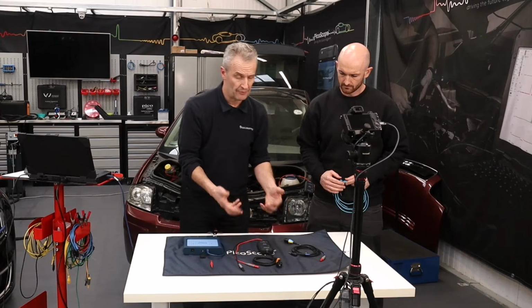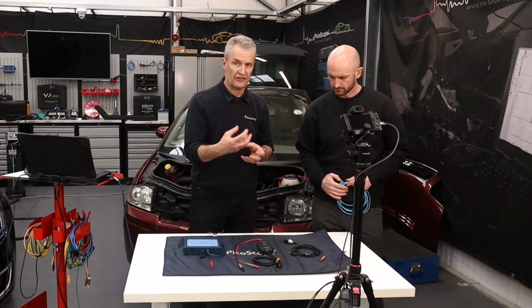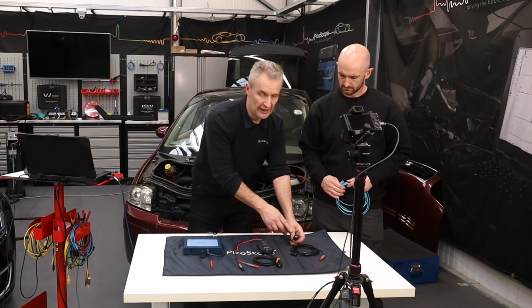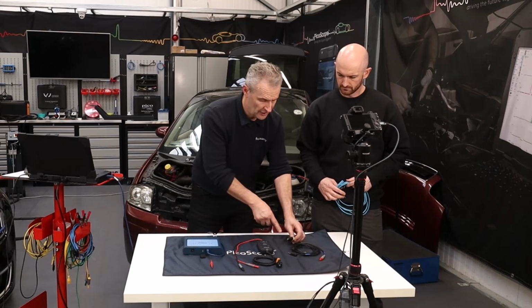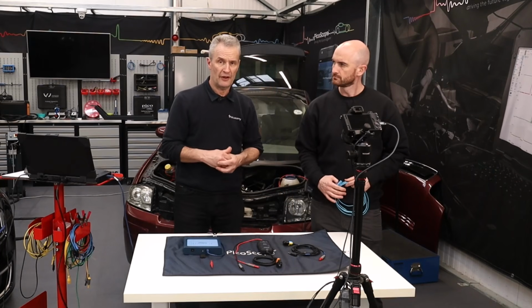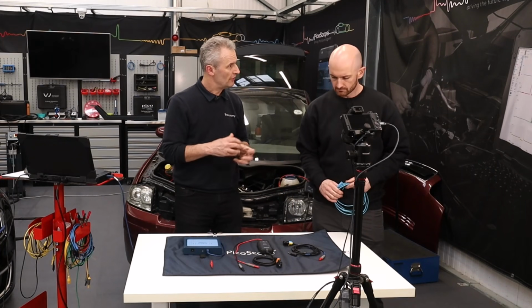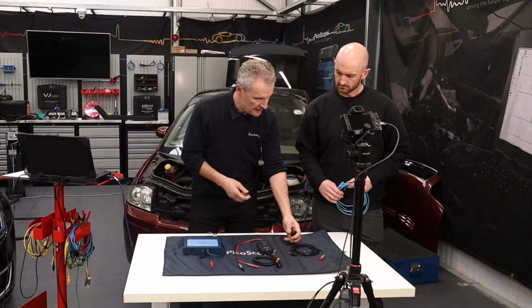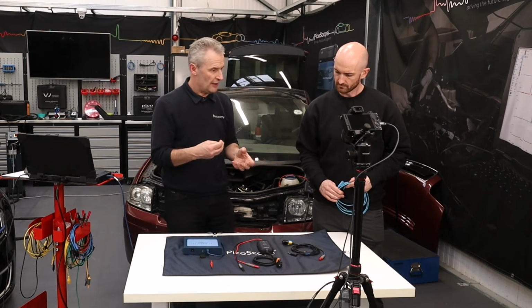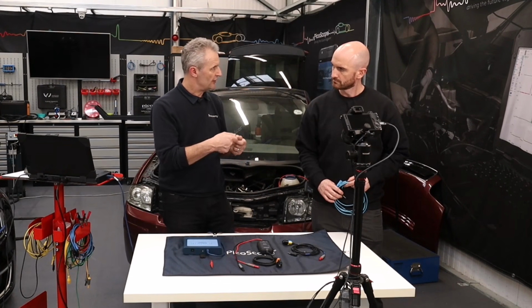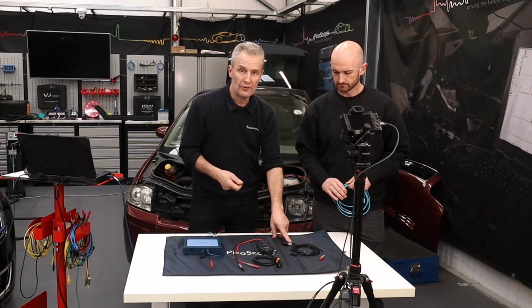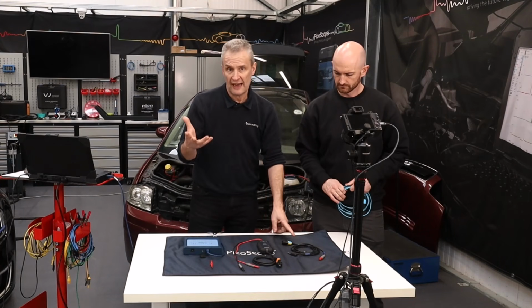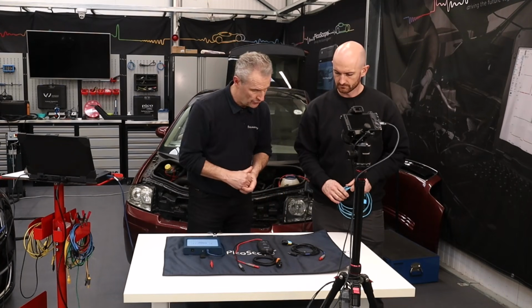We call it a ×10 probe, it's a division, because when it gets to the software, the software knows what we've connected because it's BNC plus. The software will then multiply the signal by 10. So as an end user, thanks to using BNC plus, we don't have to notify the software we've got an attenuator fitted. It already knows what probe is connected, so it handles the attenuation for us.